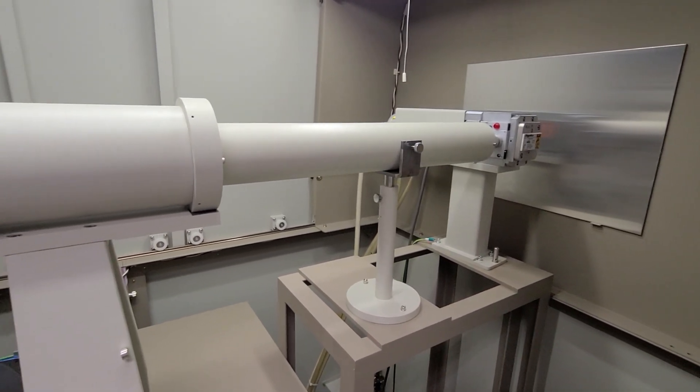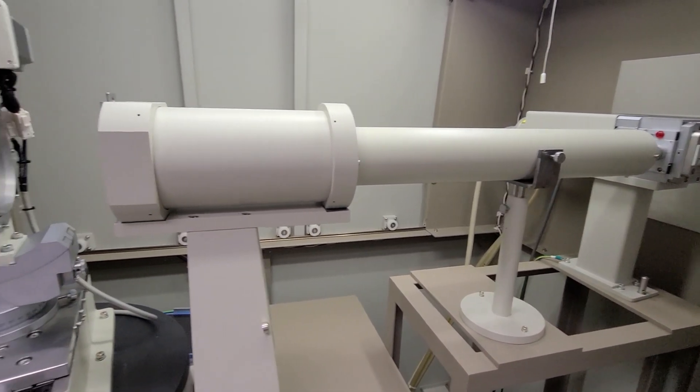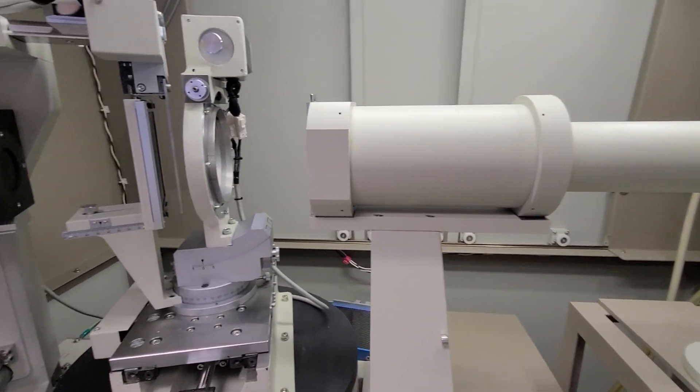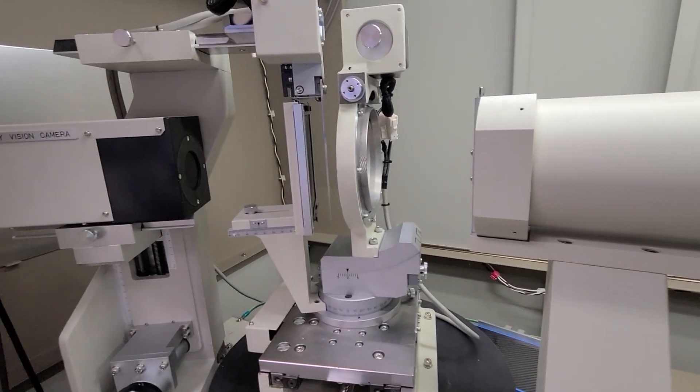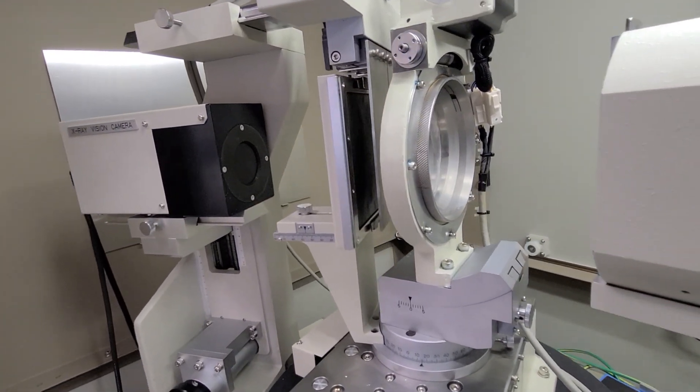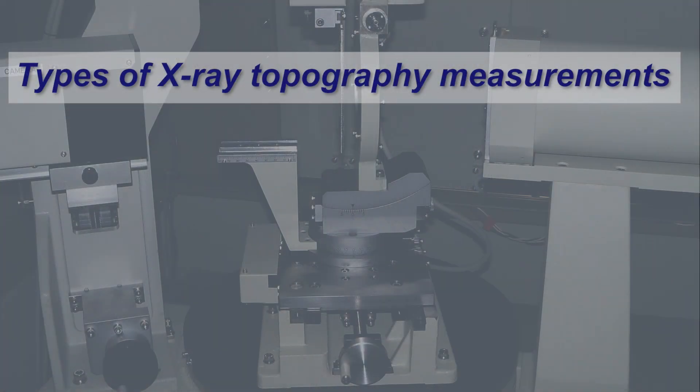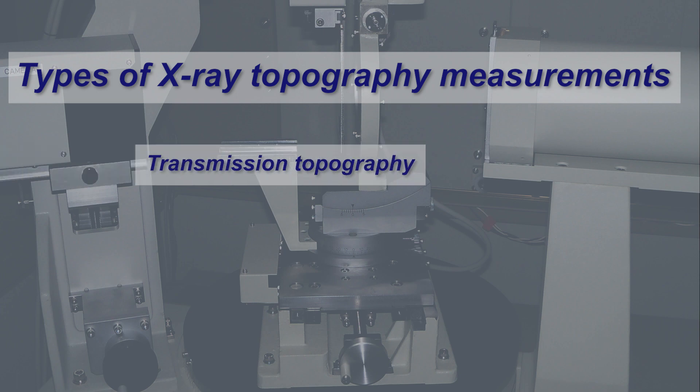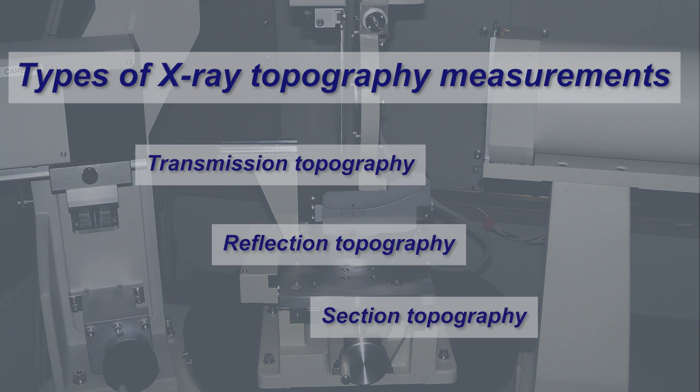We can measure samples up to 100 millimeters in diameter with each image. For larger samples, multiple images can be stitched together to form a larger image. There are multiple types of X-ray topography measurements: transmission topography, reflection topography, and section topography are the most common.